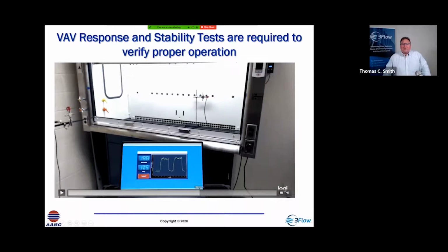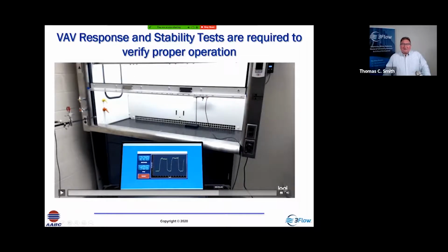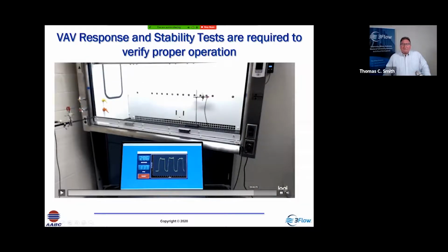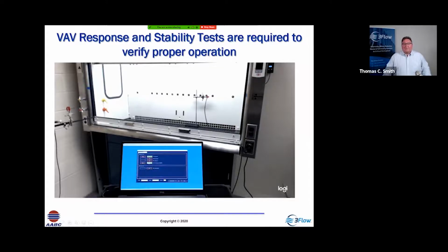So as we move along, I'm speeding it up a little bit, obviously, because you can tell I don't move that fast. But this allows us to look at the modulation of flow. We do 3 cycles of opening and closing so that we can look at the repeatability of the controllers in going from sash closed to sash open. We also look at the speed of response. So let's look at this in a little more detail.